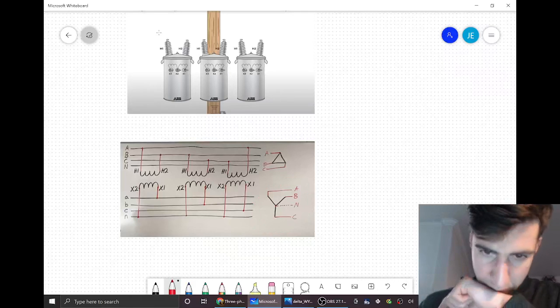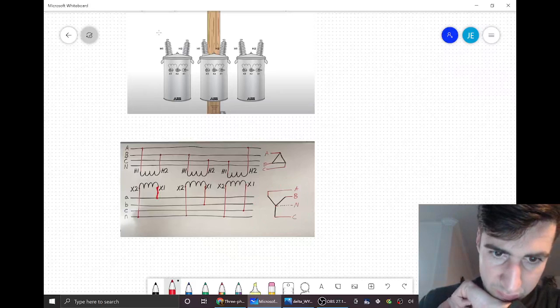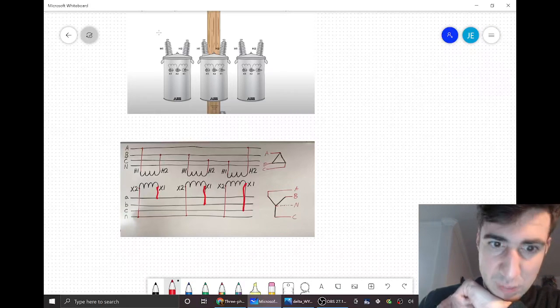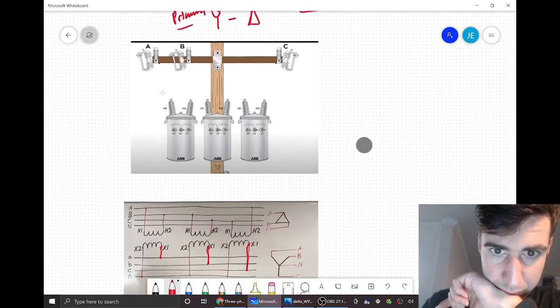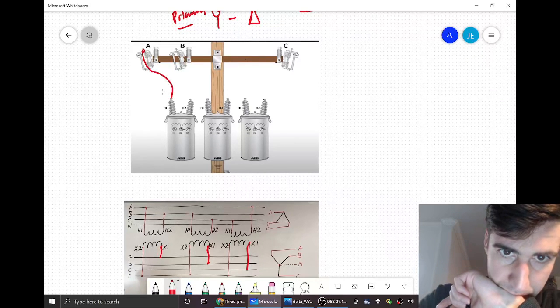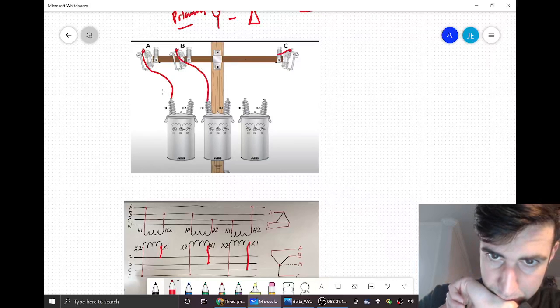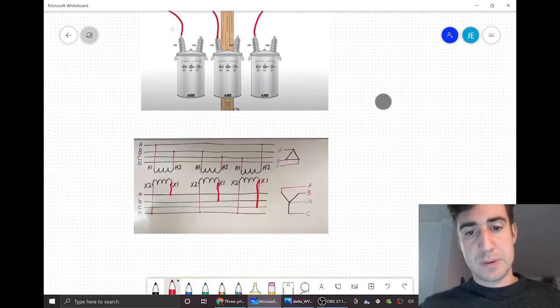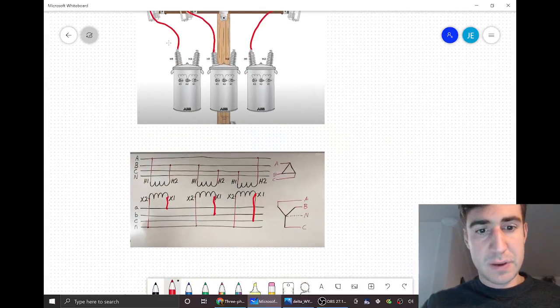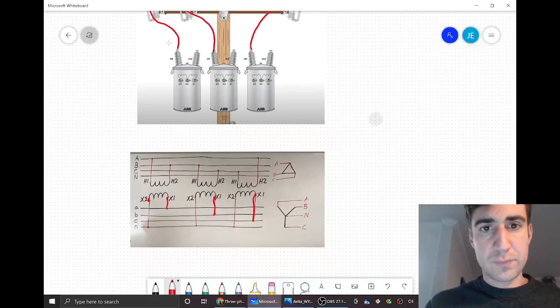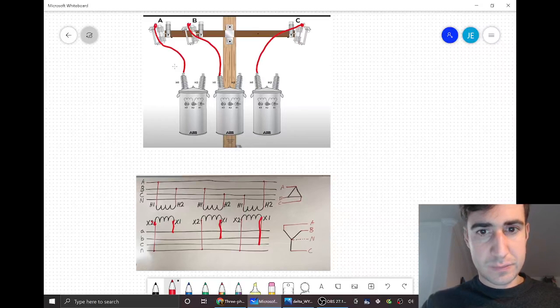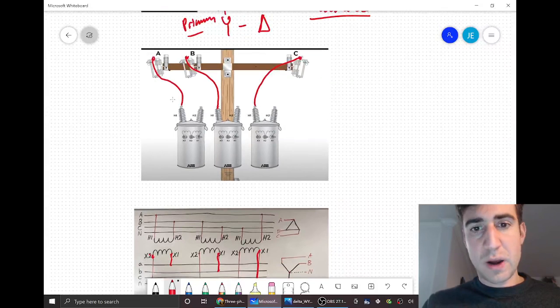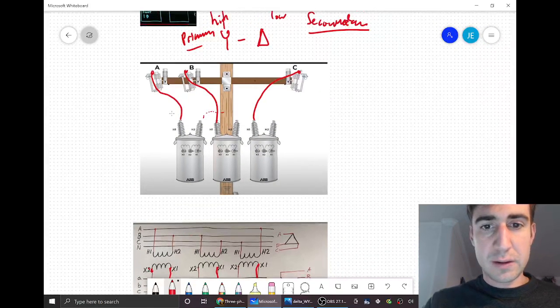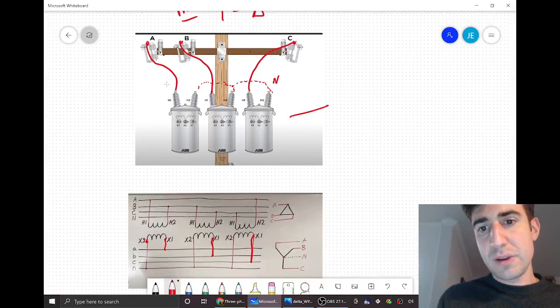And each one of those, one side of the coils, is going to connect A, B, and C. So let's do that now. Great. Now, the other side of this bushing is going to connect. The other bushing is going to connect to the neutral. But on the high side, that neutral is actually just going to be floated. So I'll draw a dashed line. Right? And this is our neutral. So now down here, these are the coils of our delta.